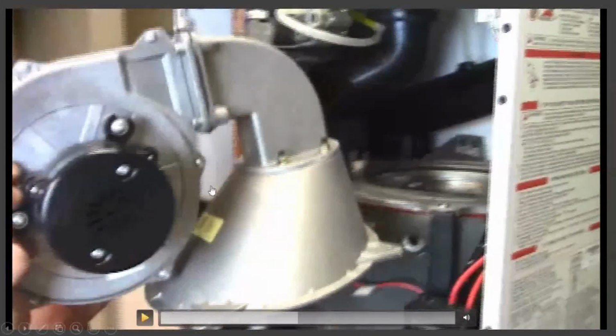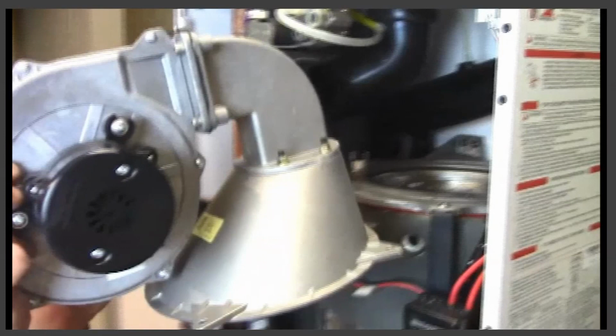All right, I'm pausing the video right here. On the 140, we had talked about removing the 4 bolts to pull the blower from the neck to the burner arm. On the 140, there is a mesh screen in here, okay? We've had some cases with dryer vents, where you're exhausting out the back of a house, or taking combustion air off the back of the house, right near a dryer vent, and all that dryer lint is being sucked in. It will not only make it to the screen, but also potentially the burner. But on the 140, there is a screen right here.